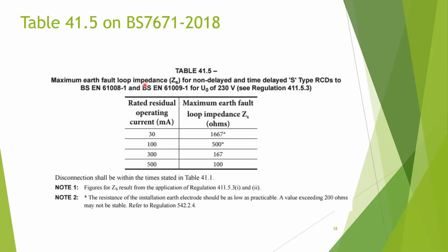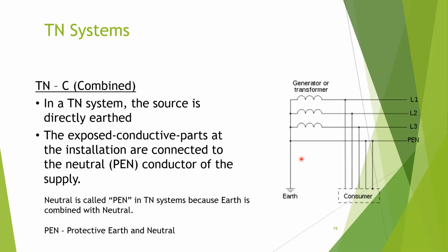BS 7671 Table 41.5 specifies these values: for 30 milliamperes the value we got just now, for 100 milliampere RCD 500 ohms, 300 milliampere 167 ohms, 500 milliampere 100 ohms. If you multiply all these values you will get 50 volts, which is the safe touch voltage. They have also specified that exceeding 200 ohms may not be stable. So keep these things in your mind. I know today's lecture is more theory, but don't worry, from the next lecture you will have to do calculations.